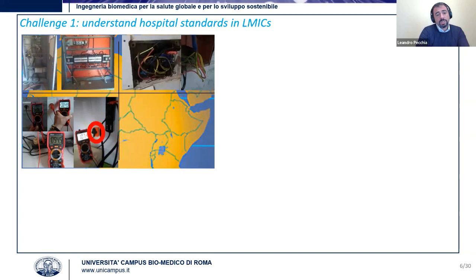The problem here was that this plug, as you can see, is a UK typical plug, and in the wall it was a Schuko, the German-looking plug. This adapter contained no connection for the ground, so this medical device, which was supposed to be grounded, is suddenly floating. This is a big issue.